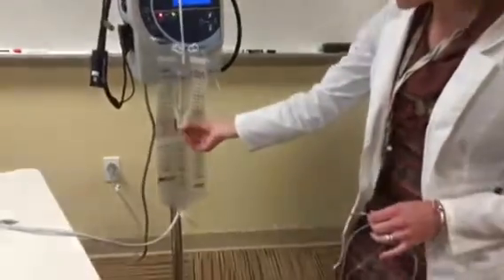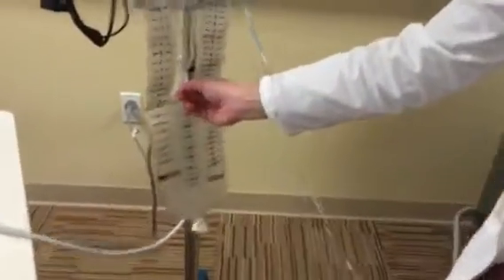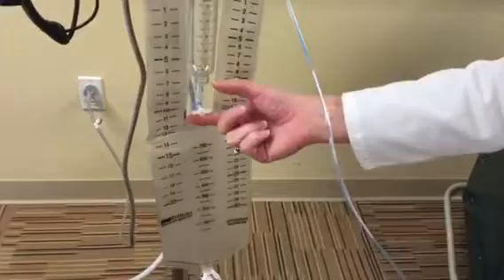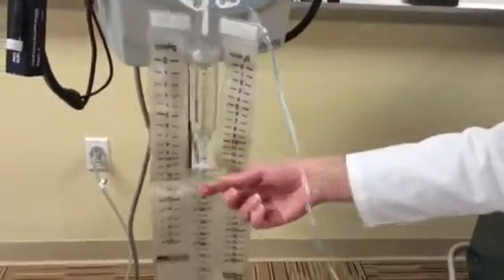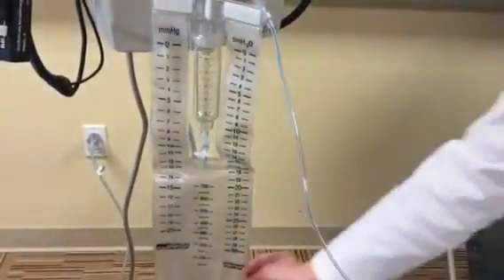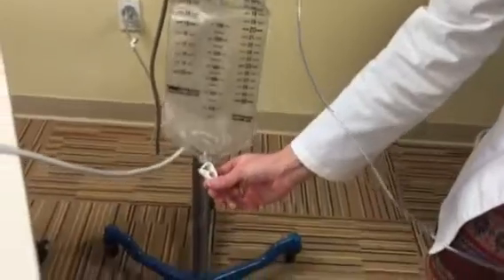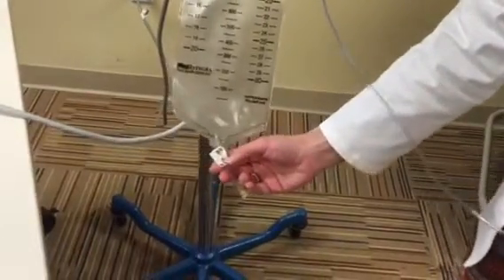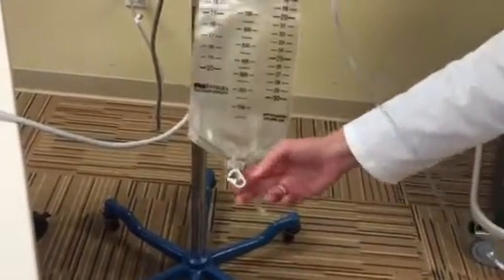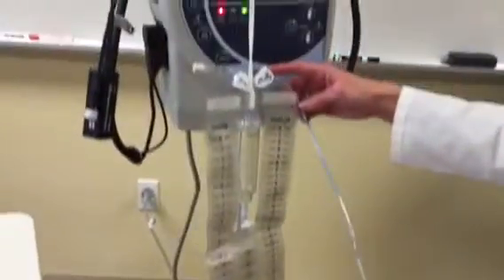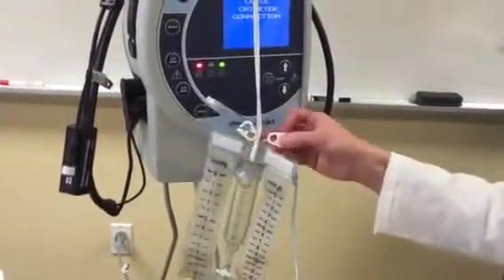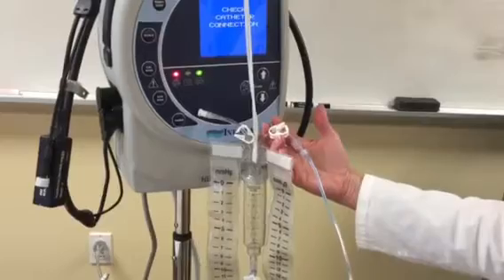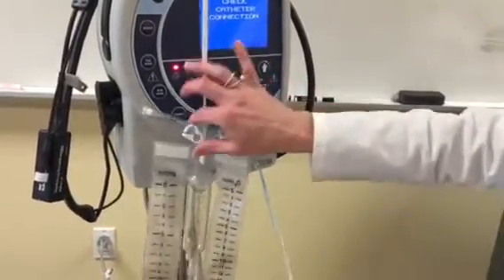Now when we're getting ready to flush it, you're going to want to make sure that this stopcock is off so we can flush it into the Buretrol just like we do with the AccuDrain. Take a few seconds to take a look at all of these pincher clamps here. They should all be open. Okay, all of them are open. This one closes off the drainage tubing itself.